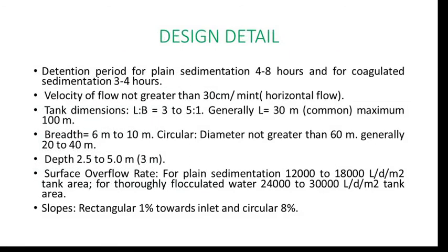Next, the design details. In these design details, you can see the detention period for plain sedimentation is 4 to 8 hours, and for coagulated sedimentation it is 3 to 4 hours. These are the various parameters required for the design of any plain sedimentation process.